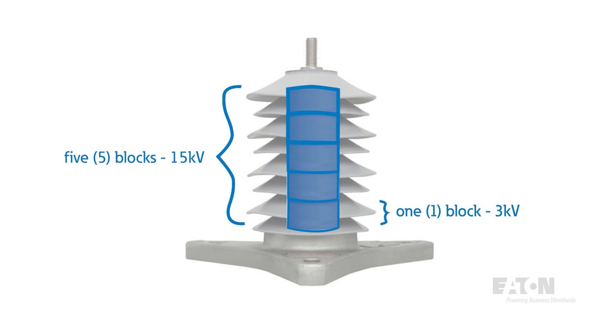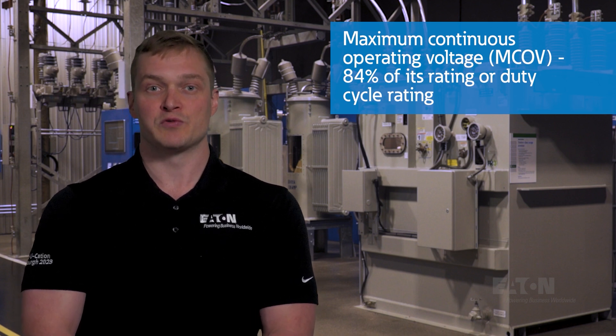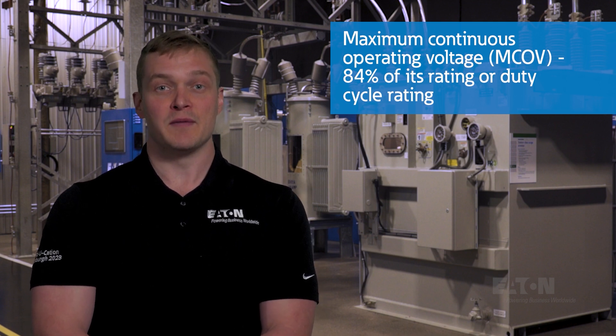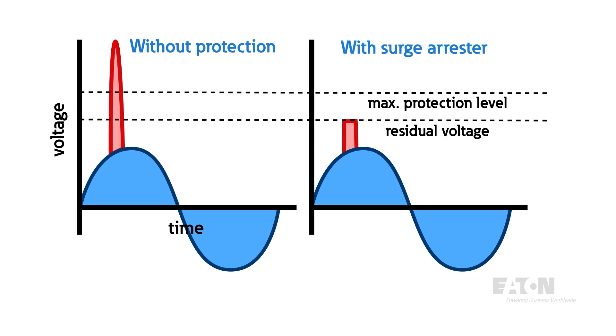In order to properly select an arrestor, utility engineers will reference its Maximum Continuous Operating Voltage, or MCOV, which represents the voltage at which the arrestor begins to conduct. The MCOV is about 84% of the arrestor's voltage rating. Aside from MCOV rating, there are also other considerations when sizing an arrestor — for instance, its discharge voltage rating. This value tells you the arrestor's let-through voltage, or residual voltage, when it operates. This is important to consider because the equipment installed in parallel will also experience this voltage rise.